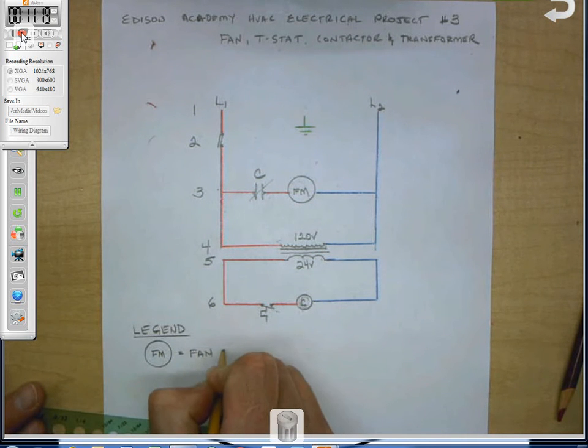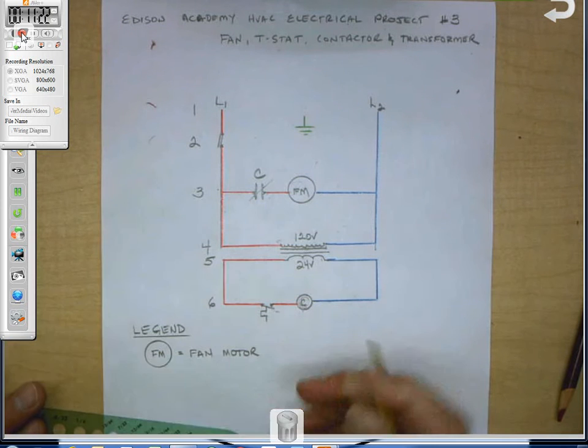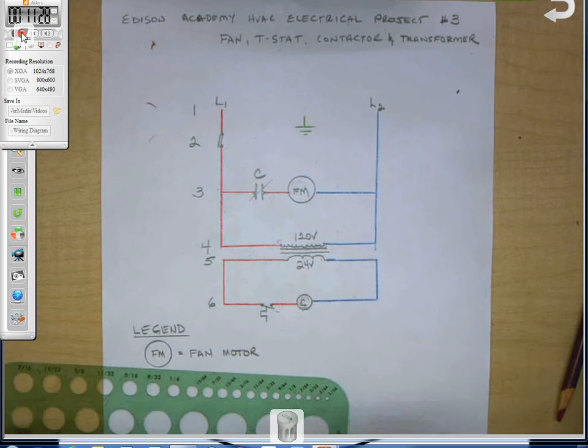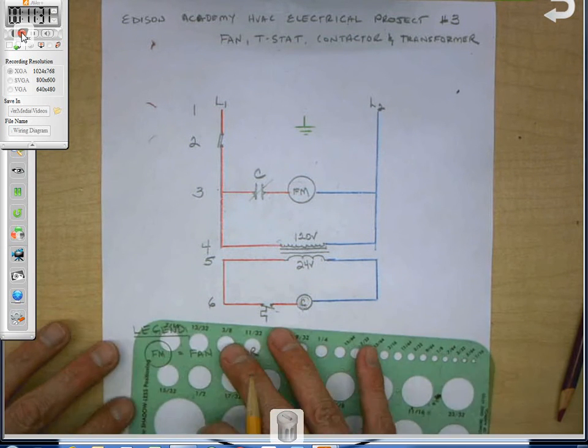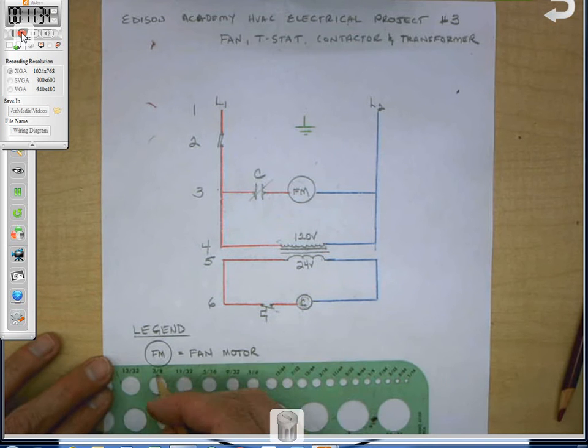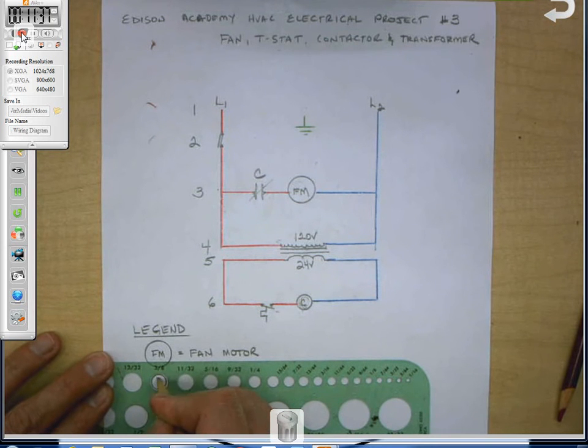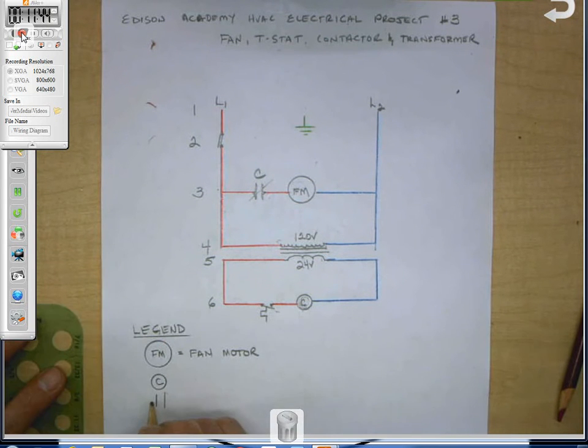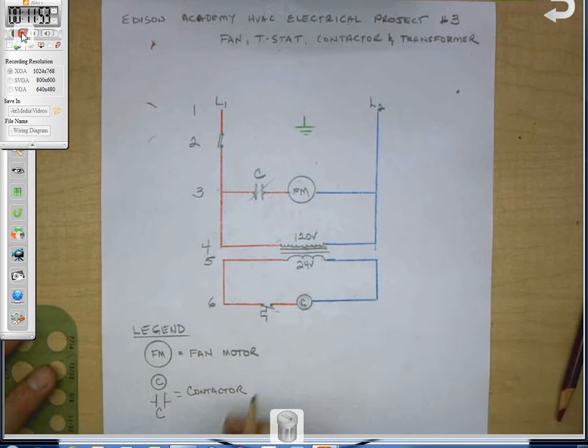I put 10, it doesn't really matter. You can even put, like I said, some put the same on either side on their drawing. But you just know that. And then some even write that this is 110 or 120 and this is 24 volt on that there. Also, sometimes they put numbers, like my power's coming in here at number one. At number two, we had a switch. At number three is the first rung where it's broken for the fan motor and has the contact coil. Number four is where the primary winding is for the transformer. Number five is the secondary winding. And number six is where the thermostat ties into the coil for the contactor up there. So they sometimes number them up like that. Let me go ahead and also identify the legend, which is this right here was the, what was FM? Fan motor. Fan motor. Now remember, this one doesn't need a cap because it's not a very high torque motor. It's a low torque motor. It just is really for moving air in a refrigerator. Alright. And then we had, I think I drew this 3/8 here. What was this piece here with a C in the middle? Yup. And it was two part. Remember that's my contactor coil. So usually somewhere, and I'm going to put them both together, there's going to be a set of contacts that go with that coil. But the whole thing is a contactor. And then the other information about it was it's a 240 volt, the most amps it can hold is 30 through it, 30 amp. And it has a 24 volt coil.